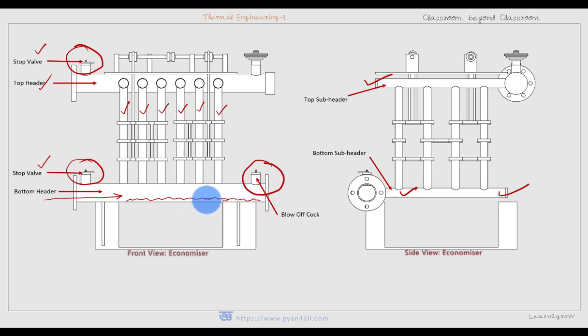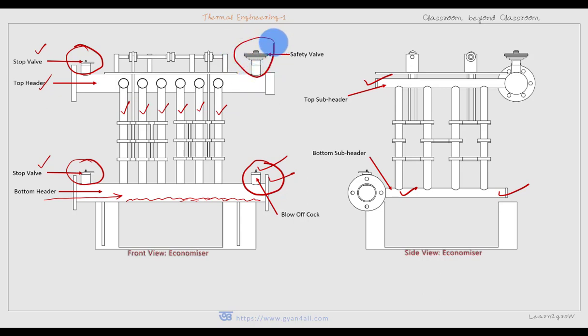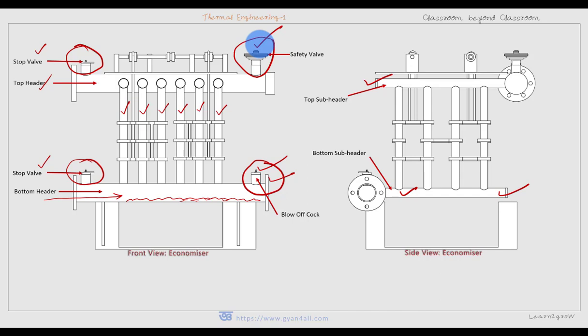The sediments or mud at the bottom header can be cleaned by operating the blow-off cock. There is also a safety valve, since this device is like a water-tube boiler — water passes through the tubes. If the water temperature increases, higher pressure may develop. The pressure inside the economizer is the same as that inside the boiler, so a safety valve is necessary. The vertical tubes connect the top header and the bottom header.